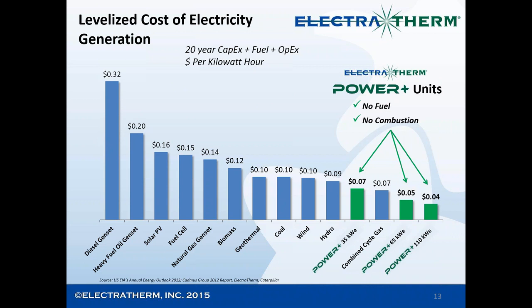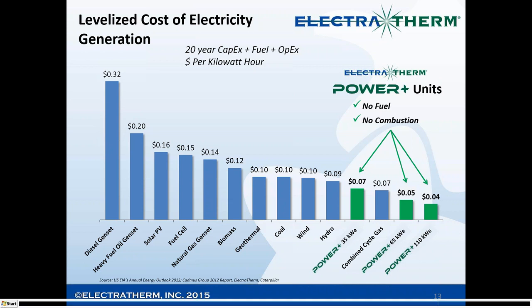We're actually commissioning one today down in Guantanamo Bay on the Navy base. The focus there is savings from making power off the waste heat. If you give me enough waste heat to make 35 kilowatts, we're at about 7-cent power. If you give me enough waste heat to make 65 kilowatts, I'm at 5-cent power. You can see the economies of scale as you go up larger, up to 110 kilowatts, our largest machine for now, and that's about 4-cent power.